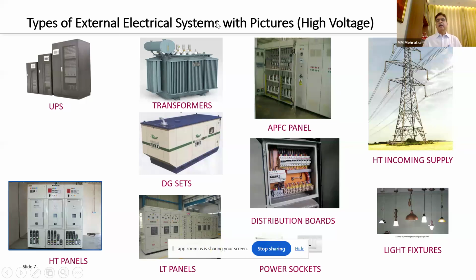Now, another window has been opened. It is called the APFC panel. APFC is the Automatic Power Factor Control Panel. If you remember, an inductive circuit causes the power factor to become lagging. For neutralizing that, you need to provide some capacitors in the circuit so that the power factor becomes unity. Why do we want this to be unity? Because then the power that can be used is that kilowatt.